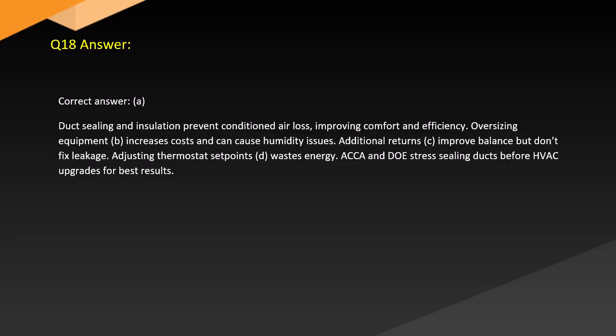Answer. Correct answer. A. Duct sealing and insulation prevent conditioned air loss, improving comfort and efficiency. Oversizing equipment, B, increases costs and can cause humidity issues. Additional returns, C, improve balance but don't fix leakage. Adjusting thermostat set points, D, wastes energy. Experts stress sealing ducts before HVAC upgrades for best results.